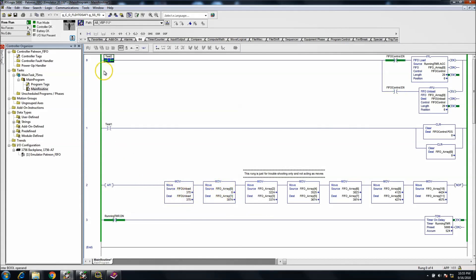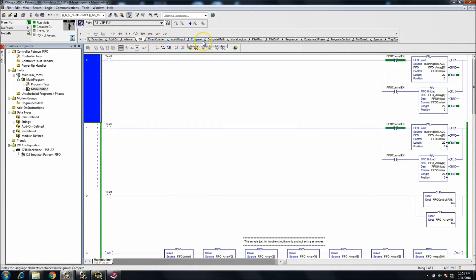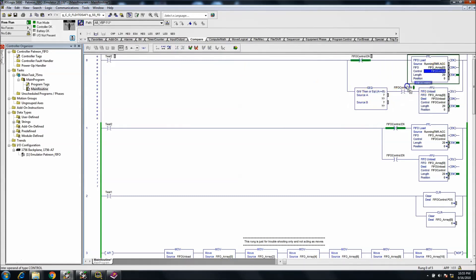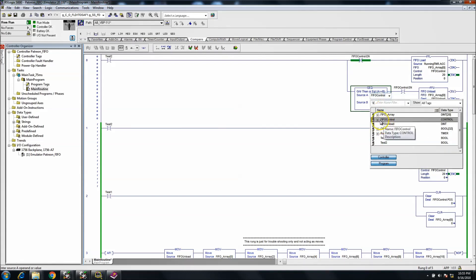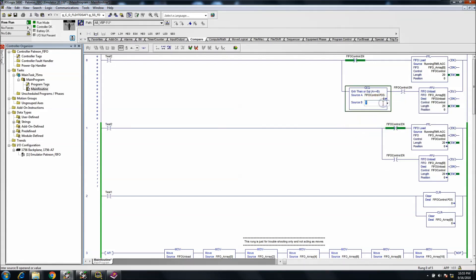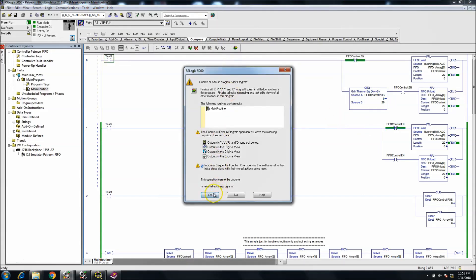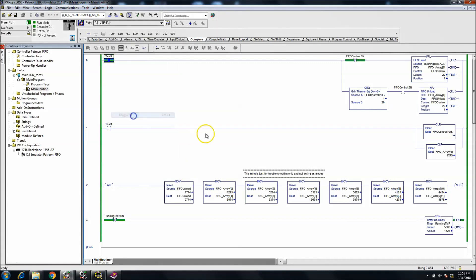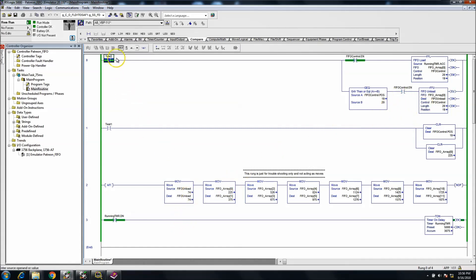Because zero is loading into the unload destination, I wanted to show you that. Before we do an unload, we should add a compare — equal to or greater than — and look at the position. If the position is equal to or greater than 20, then we definitely want to start unloading. So it will start loading, you see the data transitioning, and then when it hits 20 it's going to start unloading.